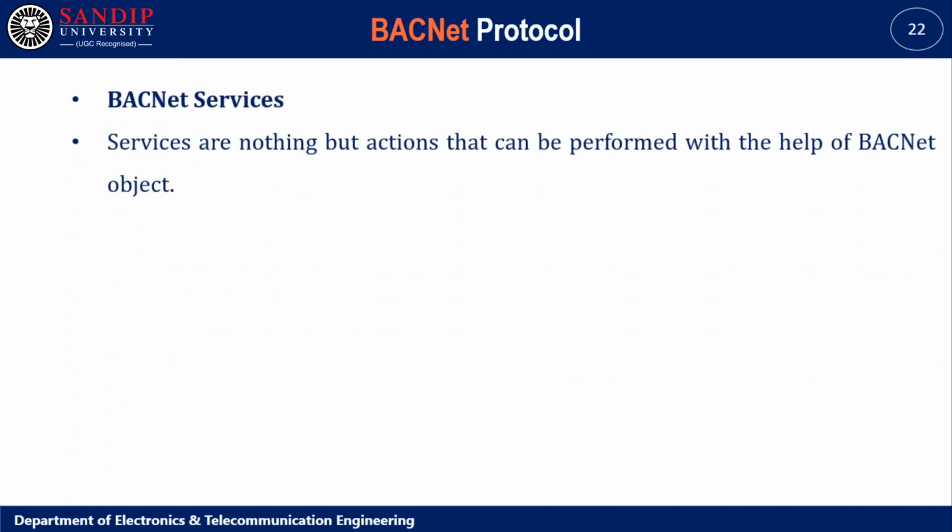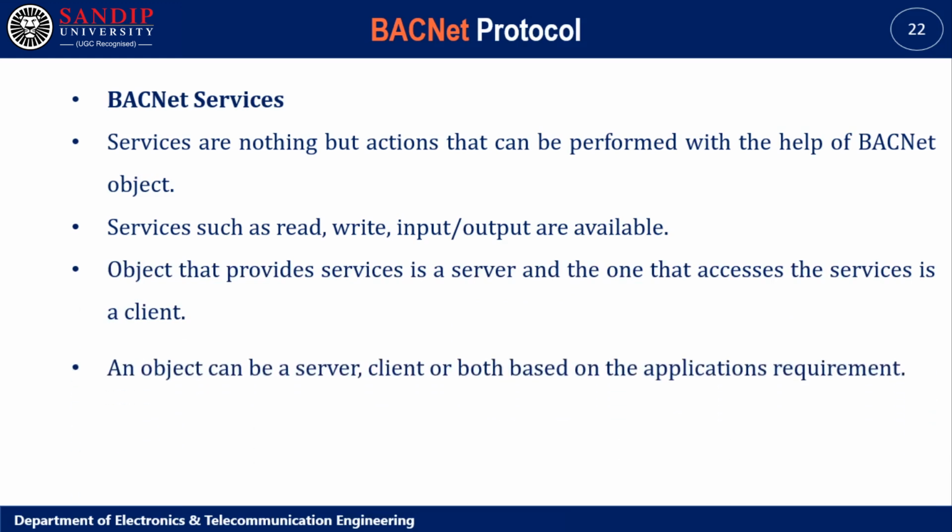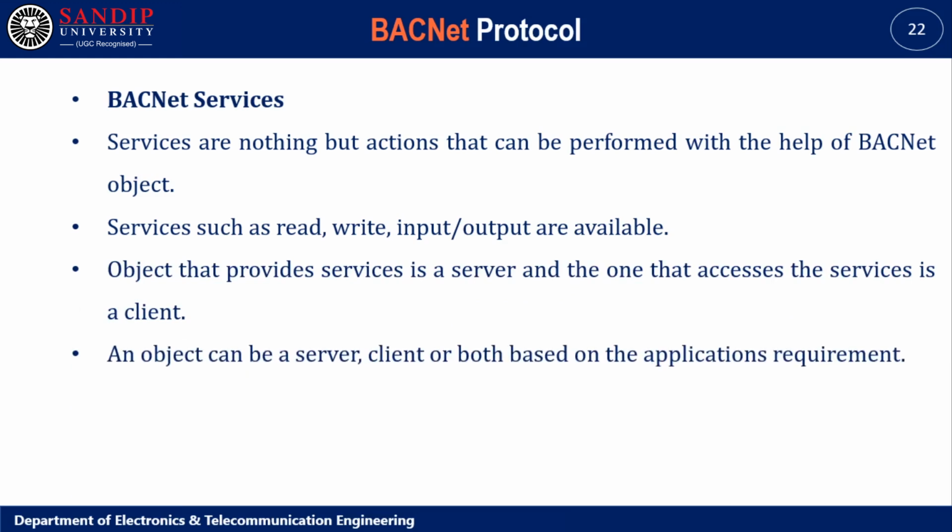BACnet services. Services are nothing but actions that can be performed with the help of BACnet objects. Services such as read, write, input, output are available. The object that provides services is a server, and the one that accesses the services is a client. An object can be a server, client, or both based on the application's requirement.